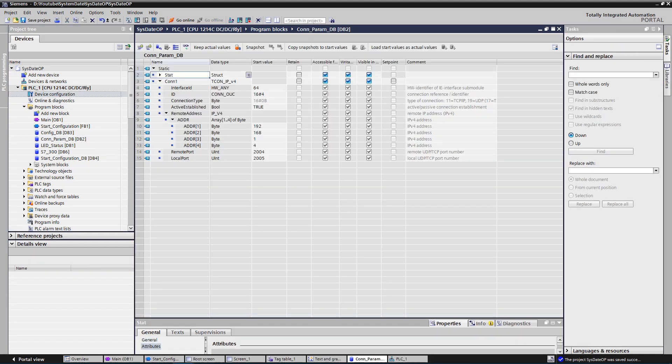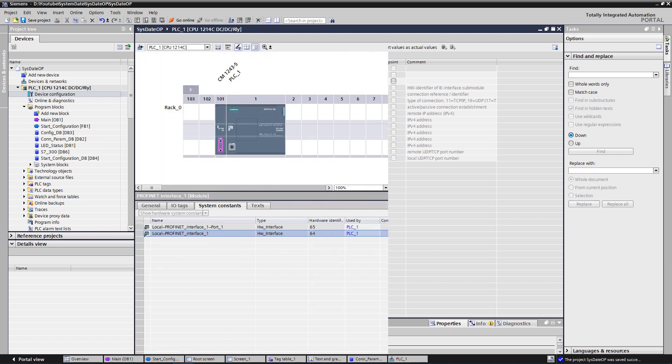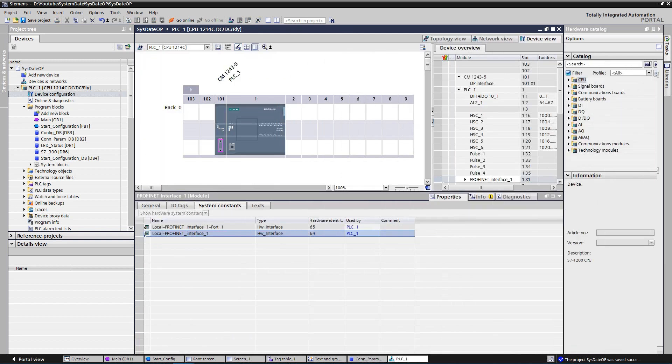You need to create a variable with the data type TCON_IPV4. The structure of this data type is as follows. Interface ID, hardware identifier of the local interface. You can find it in system constants of your hardware in the device view.